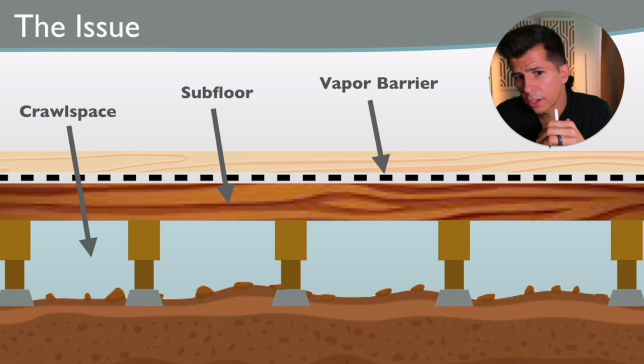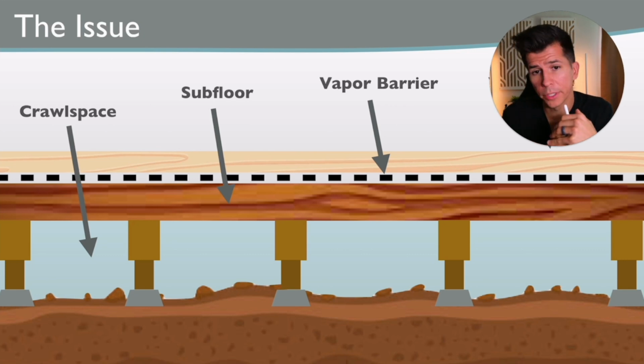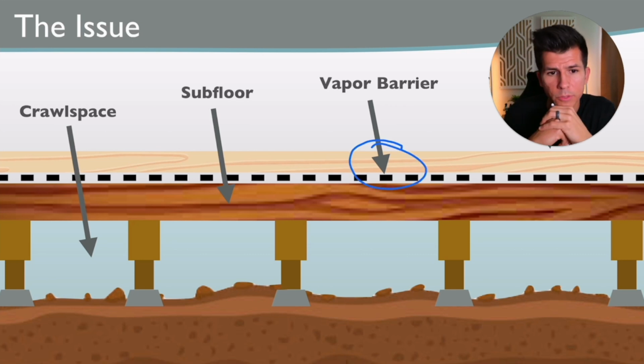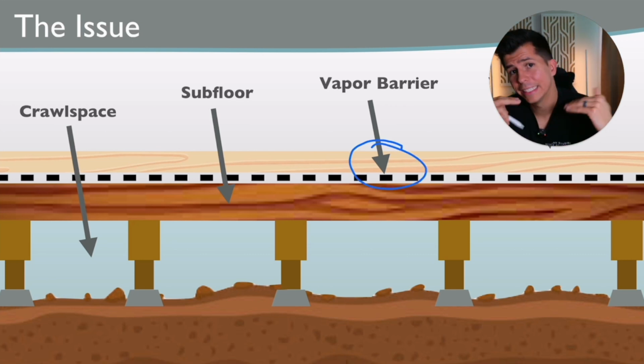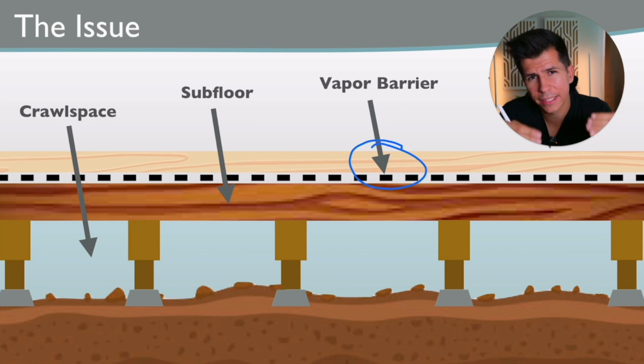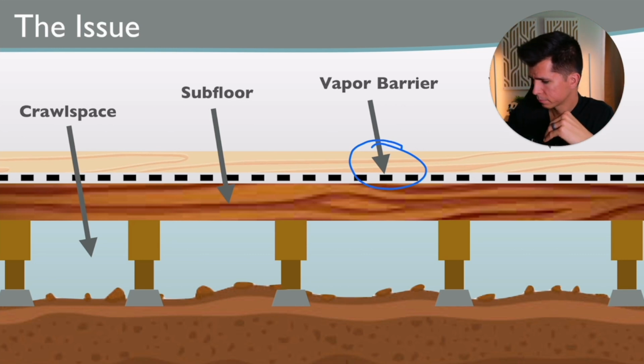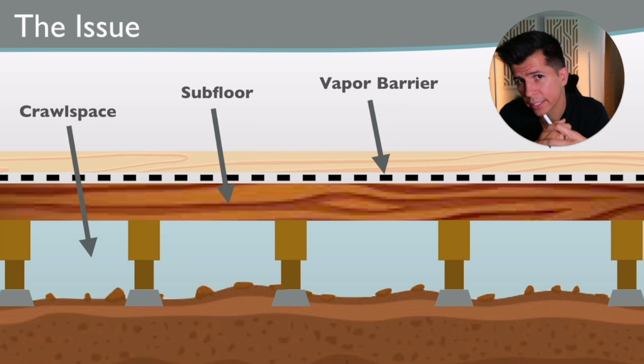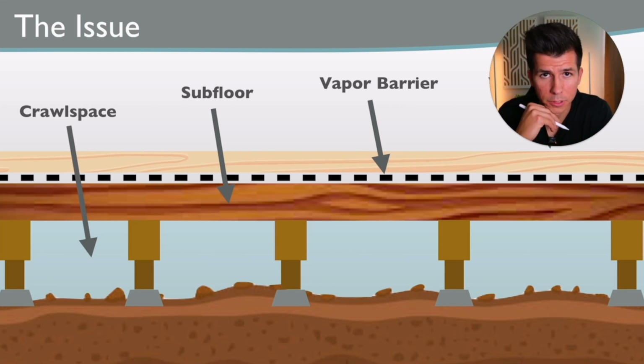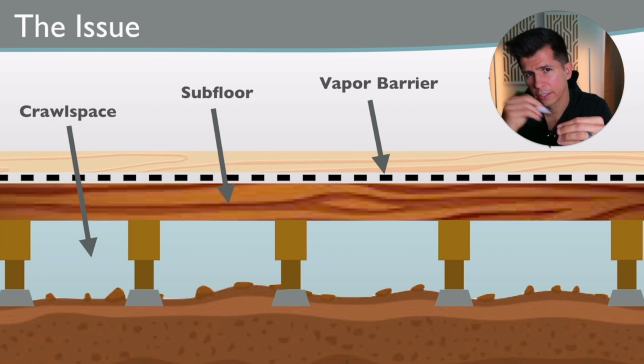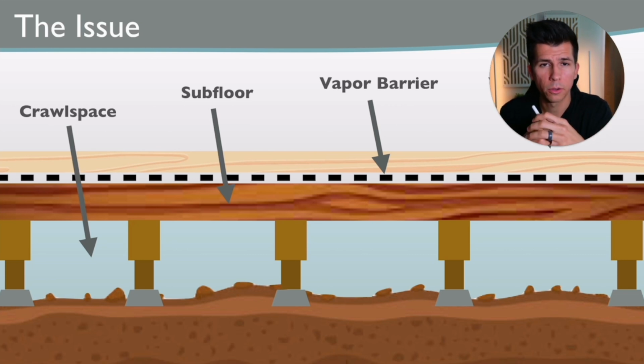The flooring installers decided to add a vapor barrier in this very leaky home. And in Florida, the last thing you want to do is add a vapor barrier right here, where they added it. Where did they add it? They added it inside the building envelope. Why is that important? Well, in Florida, we have more moisture outside than we do inside for the vast majority of the year. So if there's more moisture outside than there is inside, where do you think that vapor is going to go? Vapor pressure, just like regular pressure, goes from high to low, right?